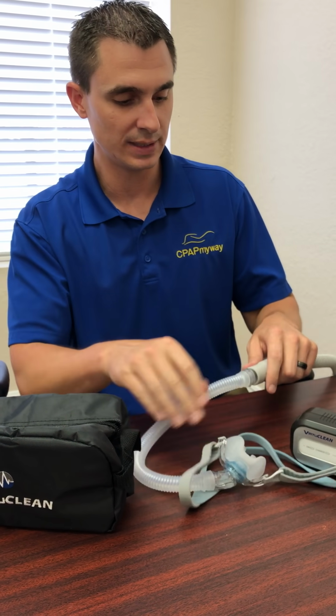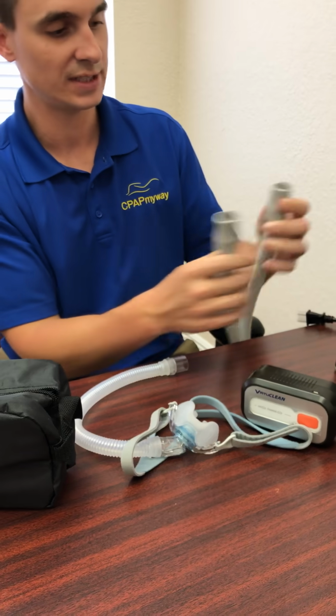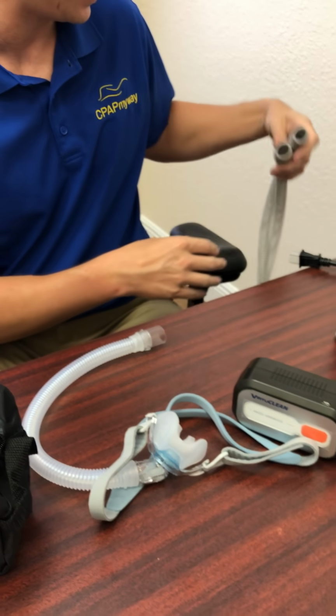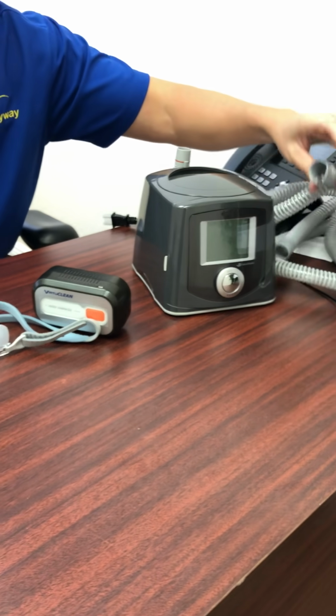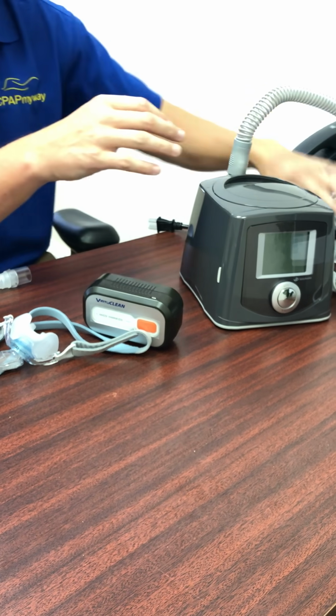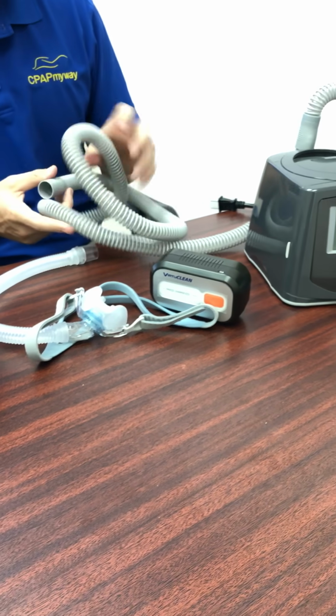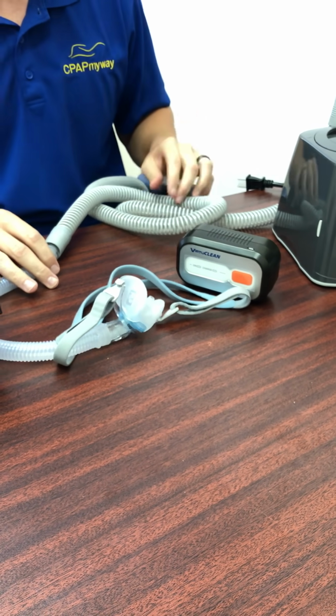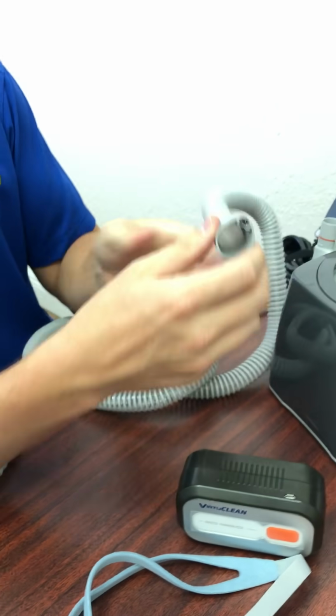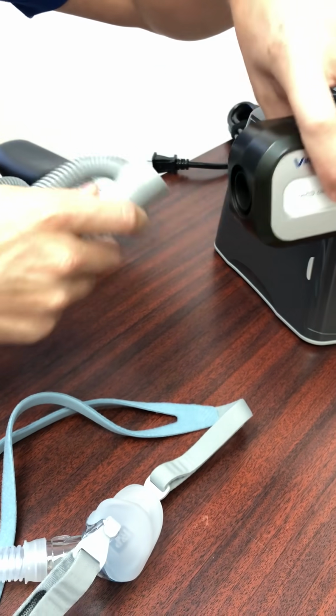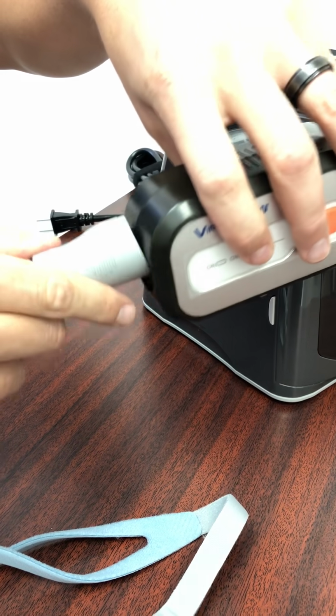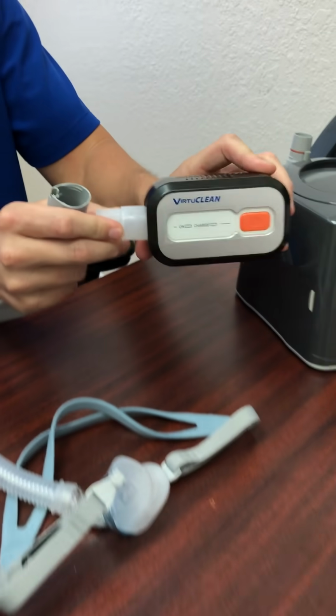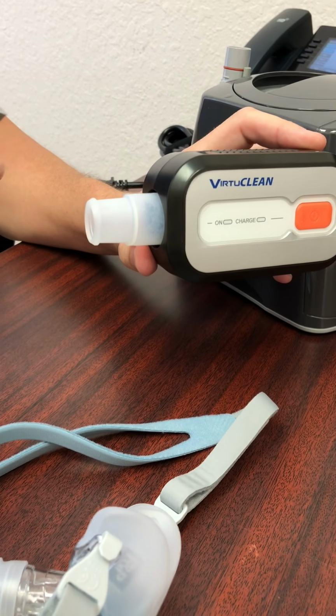So one thing we've bumped into in using this is that it works great for standard tubing. But what if you have a ThermoSmart or Climate Line tube that has the heated electrodes? So we're going to demonstrate that real quick with a ThermoSmart tube here from the Icon unit. When you're going to disconnect that, you'll notice that there's some electrodes on the tubing that will not allow it to plug onto the recessed port there on the side of that Virtuclean device. So what we have for that is a really nifty little adapter. All you do is pop the adapter on the side and it extends that little junction out so that you can plug your heated tube right on there.